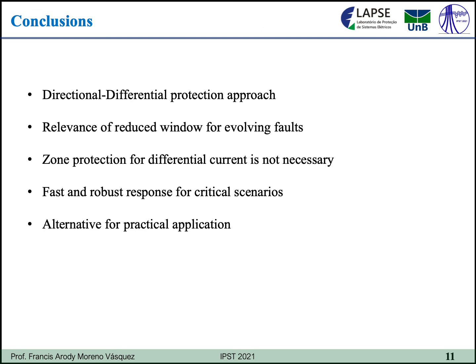Finally, among the main conclusions of this work, we can say that the proposed algorithm successfully works by using the directional and differential principles for busbar protection application, by using the incremental differential currents calculated with a half-cycle window. The window size choice is critical for dealing with evolving faults. On the other hand, this technique needs the status of circuit breakers and disconnect switches to correctly identify the feeders to be disconnected in the presence of a fault.